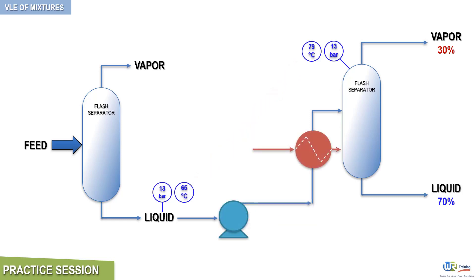However, as we know, pumps increase the pressure of the liquid being handled. So we need to add a third piece of equipment to create a pressure drop, in order to bring the pressure back to 13 bars, as that is the required operating pressure of the second flash unit. This can be accomplished by installing a control valve at the pump discharge, as depicted here.